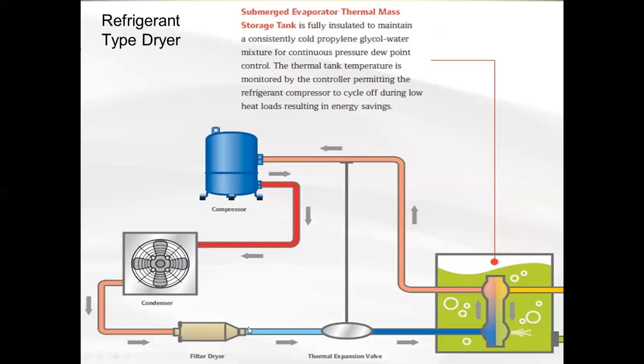and you can see the color turning more blue. This is a little bit of a pressure drop, so we get a little bit of flashing to the vapor state, which cools down everything. And then this is a big pressure drop, and so I'd say 3 to 5% of this refrigerant flashes to saturated vapor, and the rest is saturated liquid that cools down the whole flow of refrigerant to between 25 and 30 degrees. It's good and cold, and then it flows into the heat exchanger here.